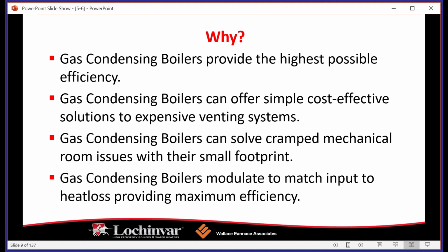And the gas boilers condensing modulate to match input, again, is one of the ways that we stack that efficiency. We take our modulation, we take our condensing, and we take the pump and flow requirements. And being able to modulate and control all three of those factors is one of the things that gives us that top efficiency, that gets us into that 90, 95, 97, 99% efficiency. These numbers are all verified. We wouldn't publish them if they hadn't been proven already.